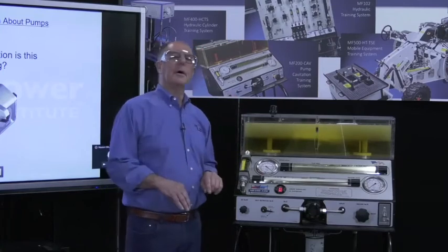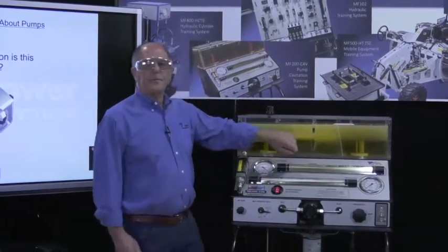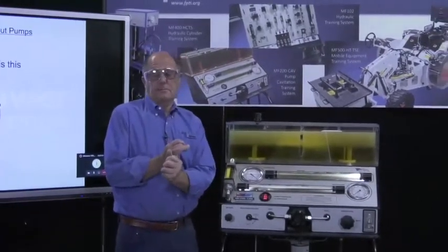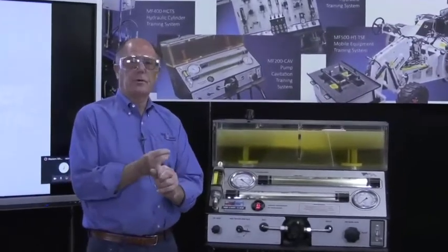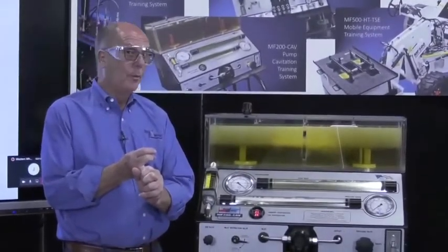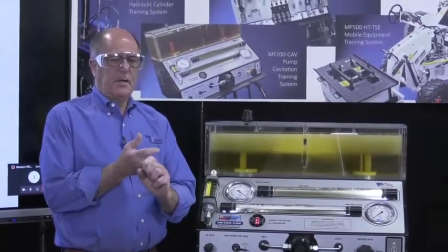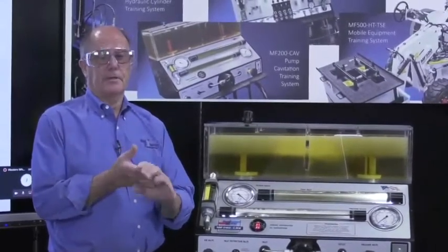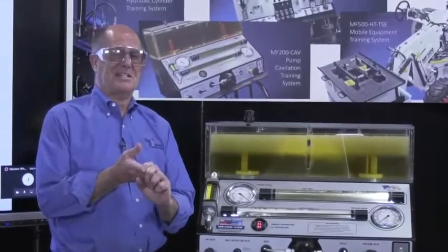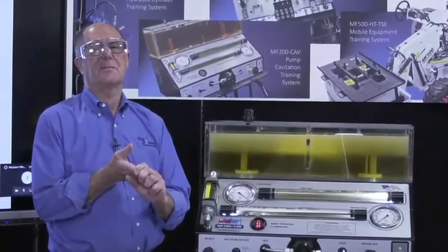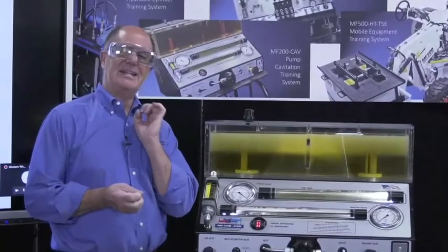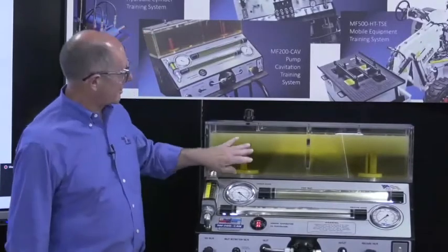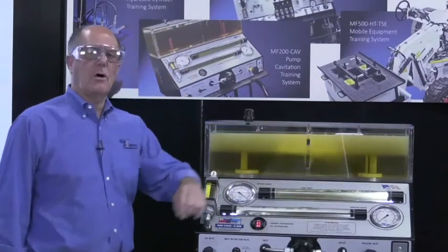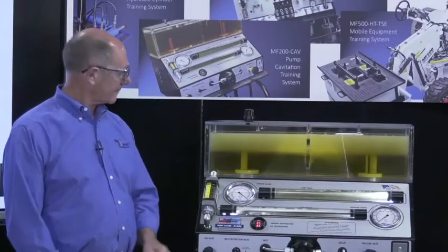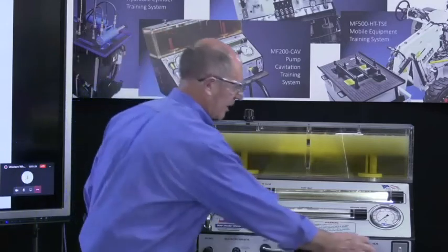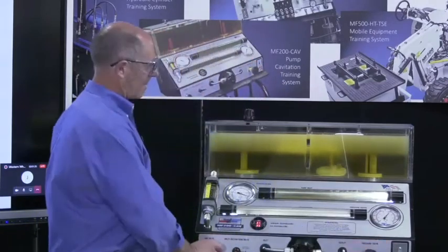All right, so back to the purpose of the oil. As you can see, this foam, first and foremost, you can't produce power with it. Number 2, you are definitely not going to be able to lubricate with it. 3, you're certainly not going to dissipate heat with it, and you're certainly not going to seal clearances. So this is a systemic disaster in a hydraulic system. Foam in the sight glass needs to be mitigated instantaneously. So as you can see, the condition of the oil, because I've now aerated the oil. So once again, let me just start this back up again. All right.